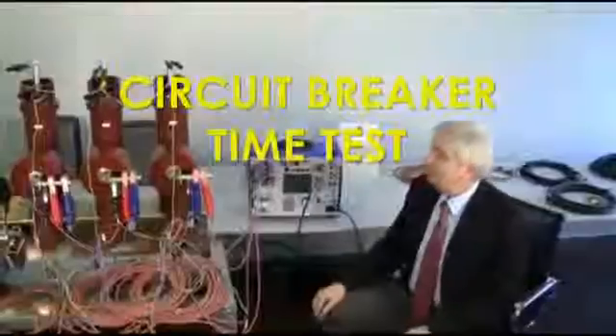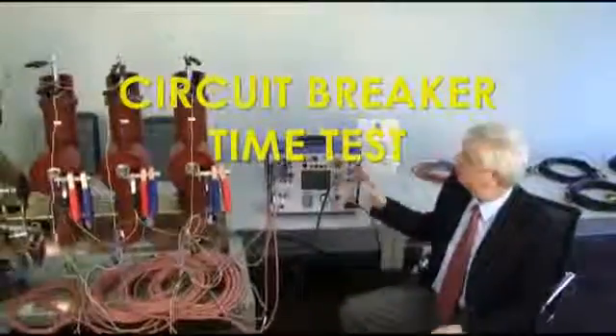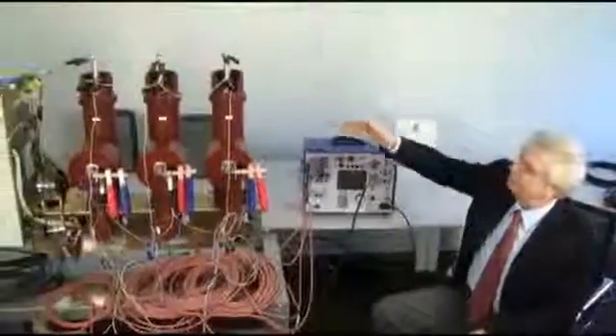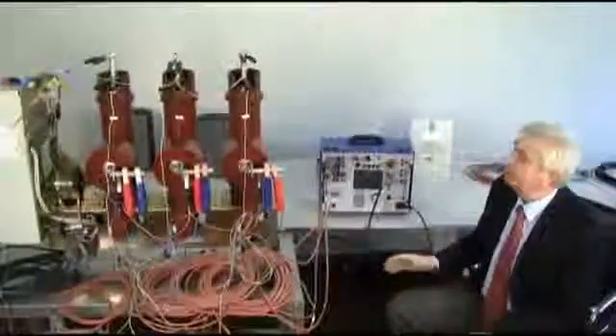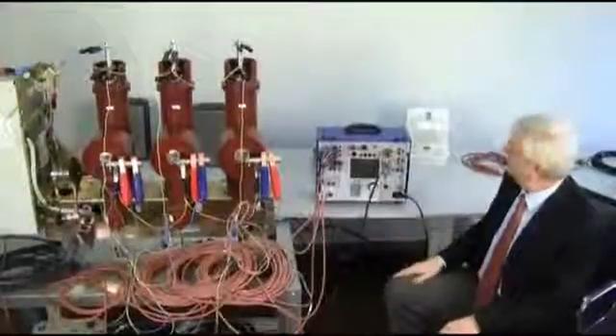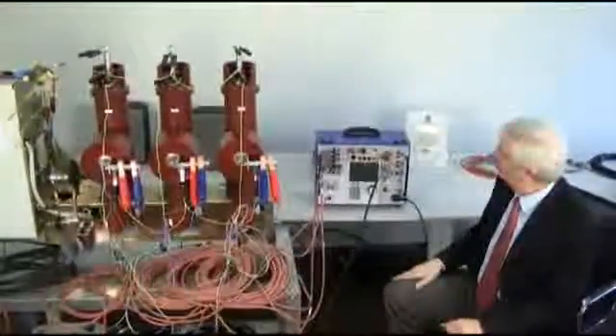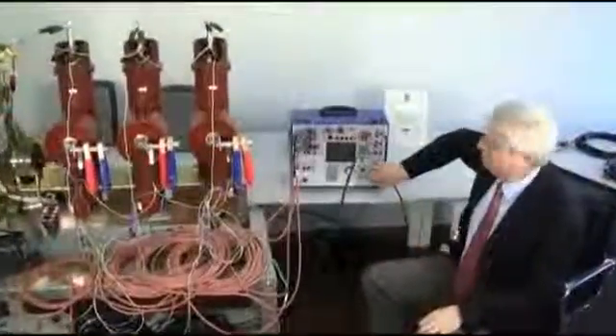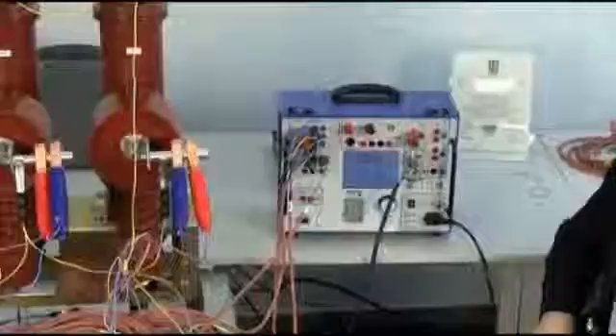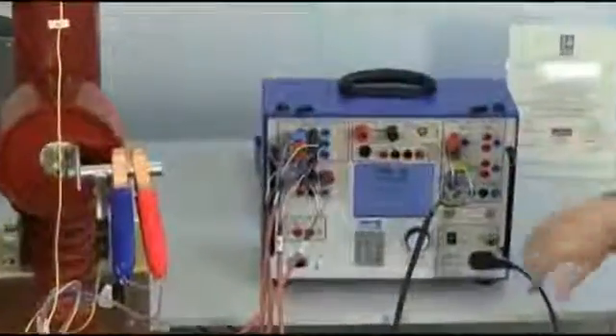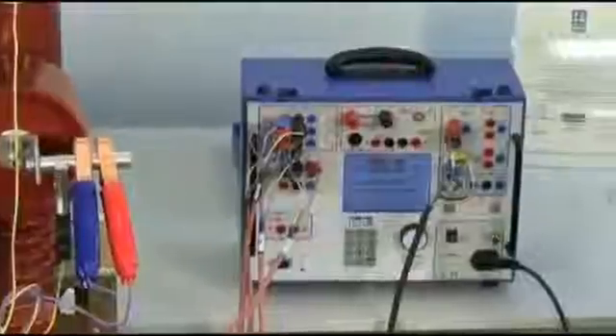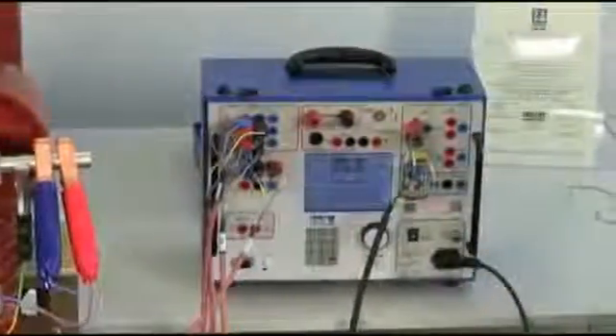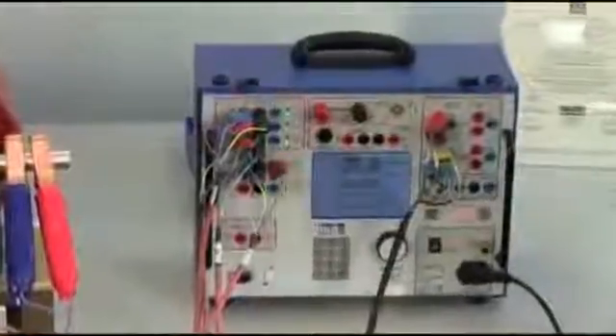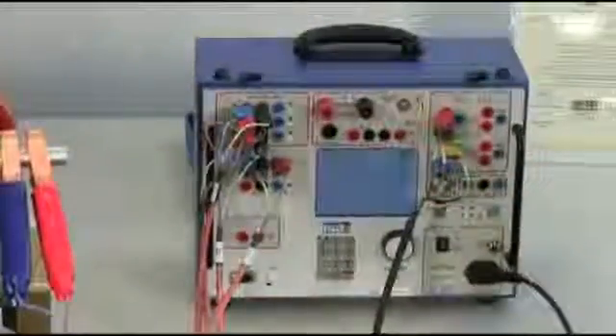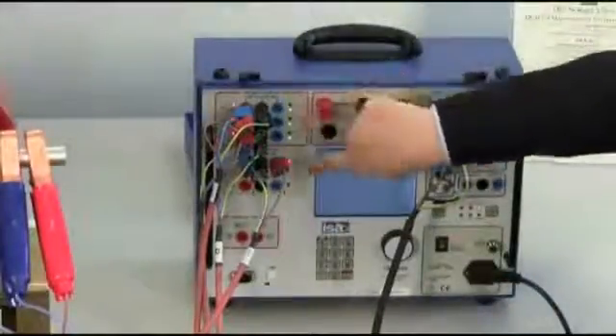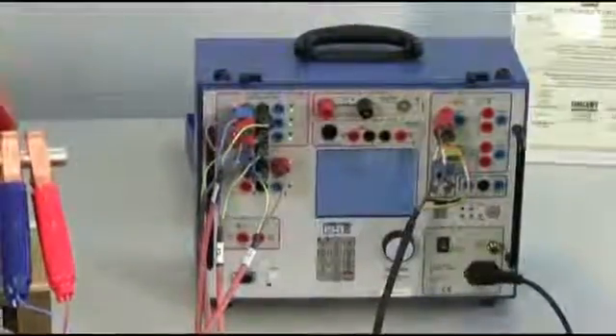Now, good morning, ladies and gentlemen. You have already learned how to connect our test set to this circuit breaker to be tested. We have the connection done, and we are about to start with the testing. The first operation I do is to power on. As I do, you see there is this diagnostic that is run. All LEDs should be on because this is the check that we do. And then once the check is over, you have here these lights telling you the status of the circuit breaker.